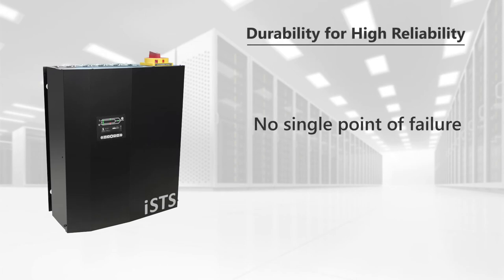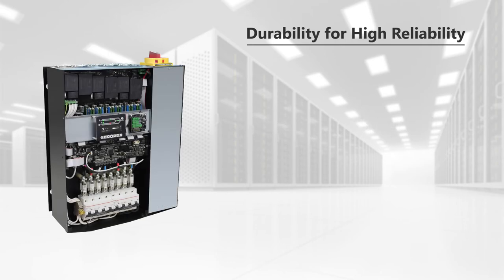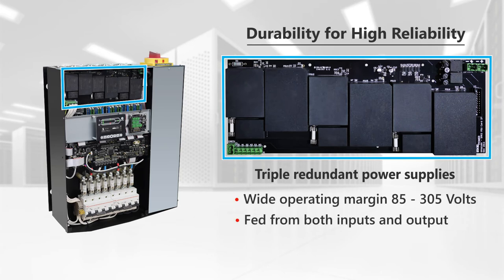The ISTS system uses multiple independent power supply buses to eliminate any single point of failure. Power supplies are triple redundant, with a wide operating margin from 85 to 305 volts, and are fed from both inputs and output.